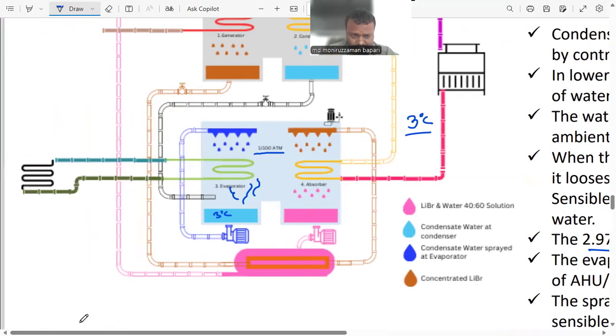Now, in the building, there are fan coil units, air handling units, or fresh air units. From these units, water comes in and feeds into the evaporator. The usual temperature here is 12 degrees centigrade. Now this 12 degree centigrade water passes through the evaporator, and whenever we spray water on top of it, as the boiling point is only 3 degrees centigrade, the sprayed water boils up and evaporates.